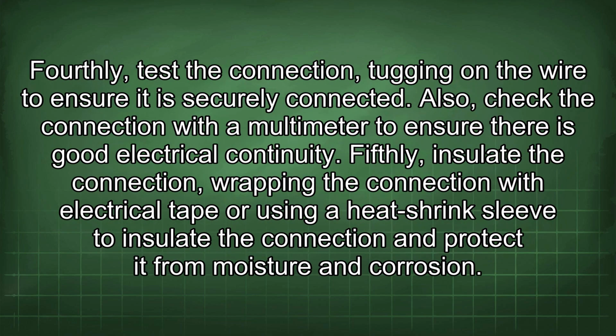Fourthly, test the connection, tugging on the wire to ensure it is securely connected. Also, check the connection with a multimeter to ensure there is good electrical continuity. Fifthly, insulate the connection, wrapping the connection with electrical tape or using a heat shrink sleeve to insulate the connection and protect it from moisture and corrosion.